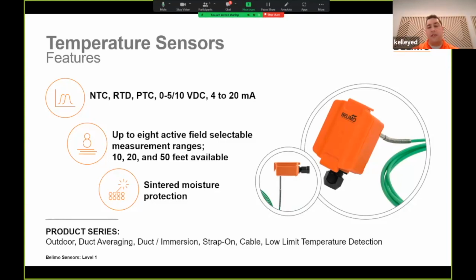So firstly, I want to quickly talk about the temperature sensors. So I mentioned seamless before. In our temperature range, we have many outputs, 10K2, 10K3, all the major passives we have. Of course, also on the analogs, you know, 0 to 5, 0 to 10. The room sensors, you can go 2 to 10 as well, right to an actuator. 4 to 20 milliamp on the current side as well. So a slew of outputs here available.